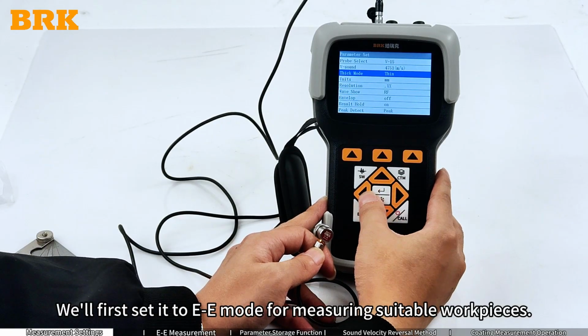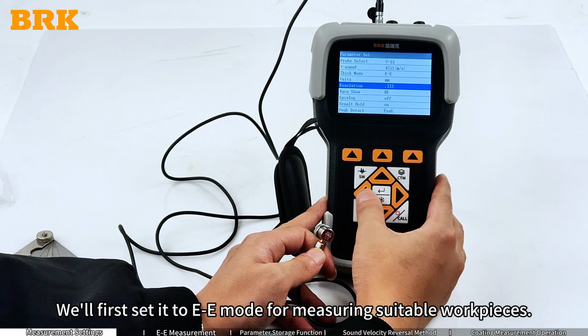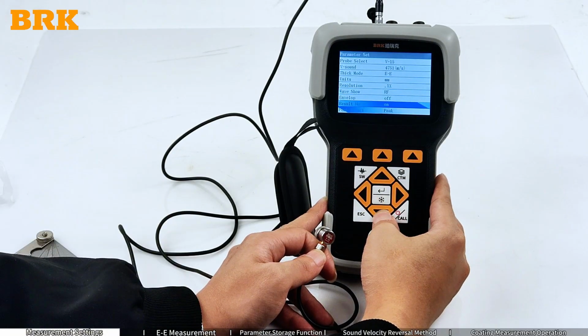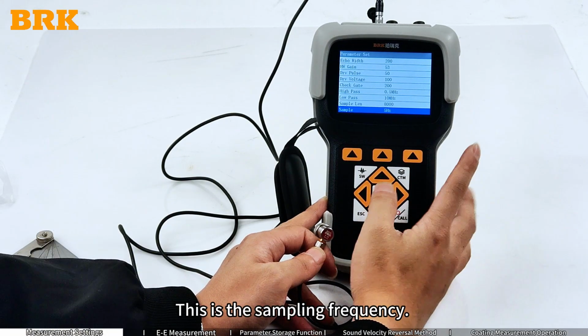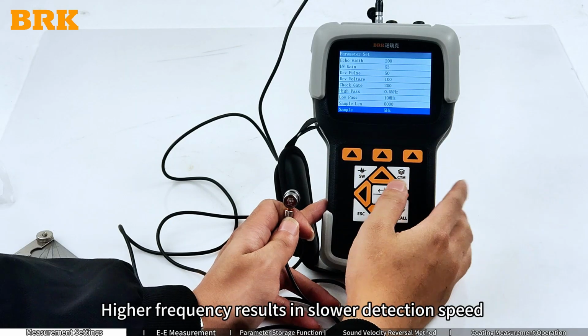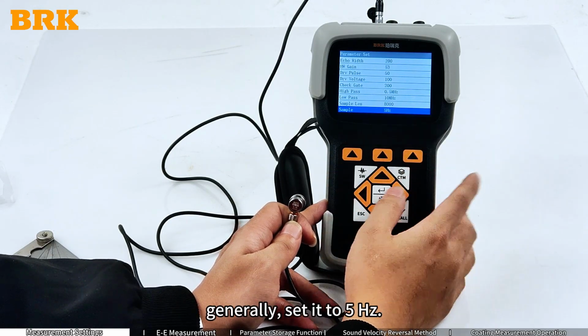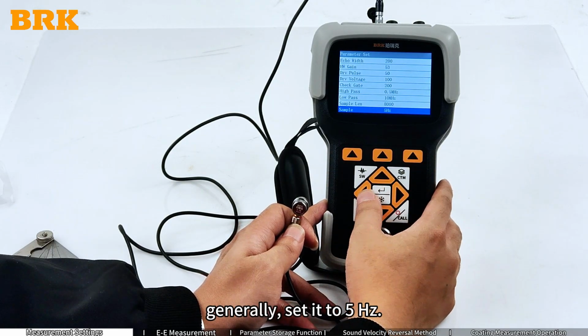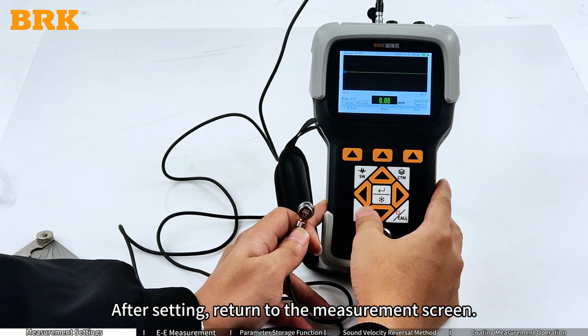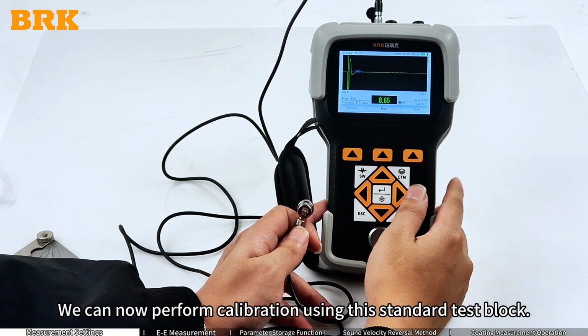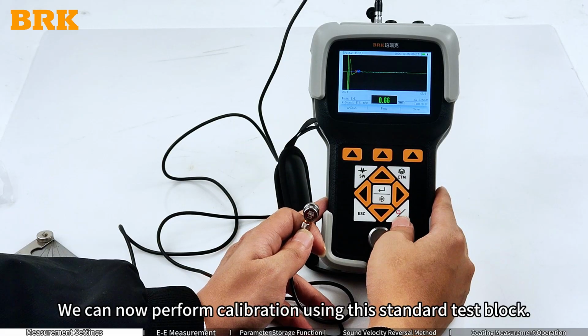We'll first set it to EE mode for measuring suitable workpieces. This is the sampling frequency. Higher frequency results in slower detection speed. Generally, set it to 5 Hz. After setting, return to the measurement screen. We can now perform calibration using this standard test block.